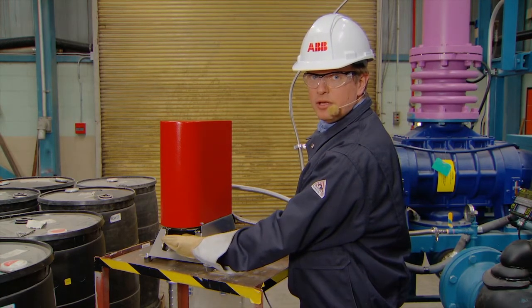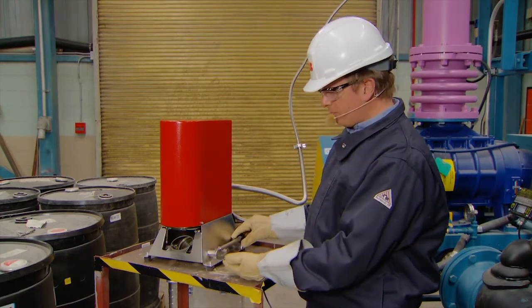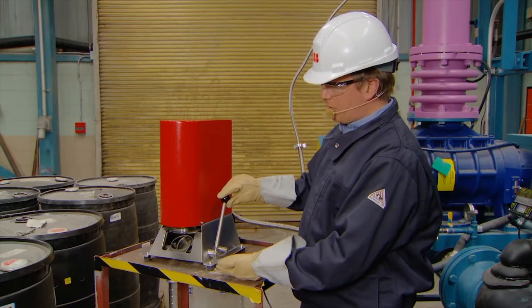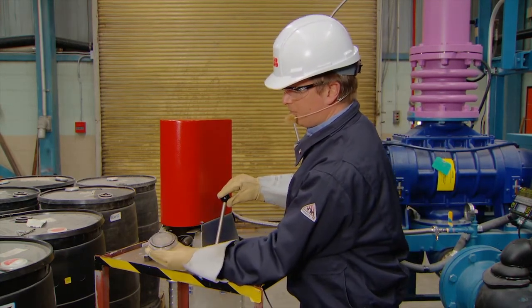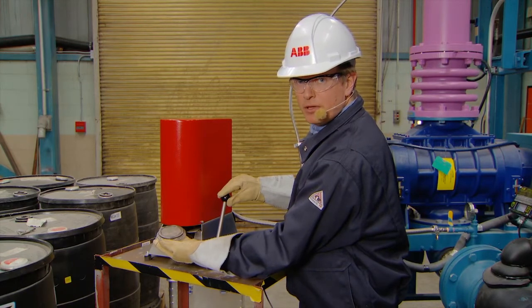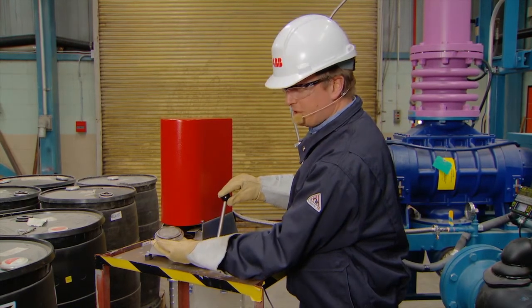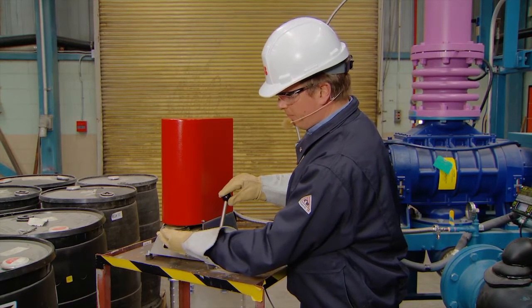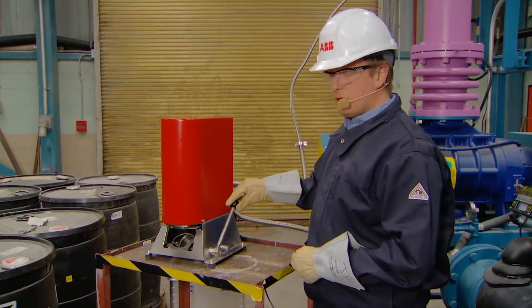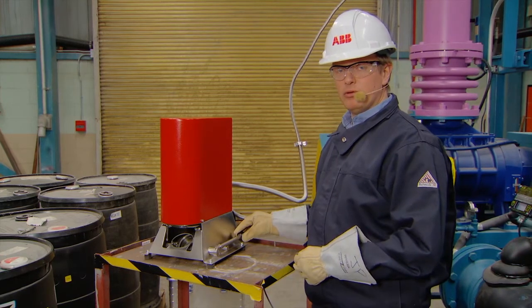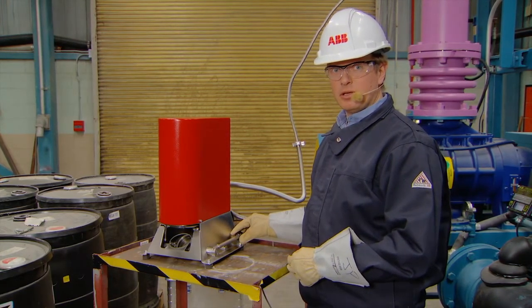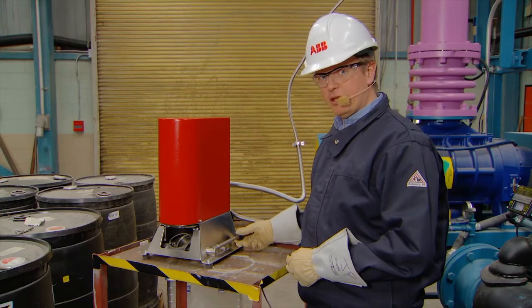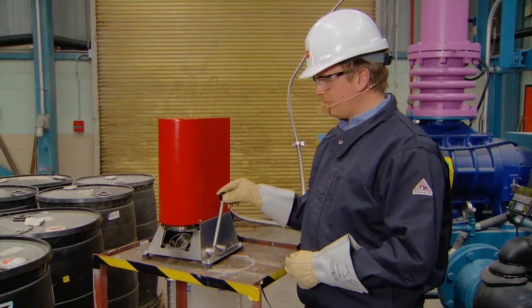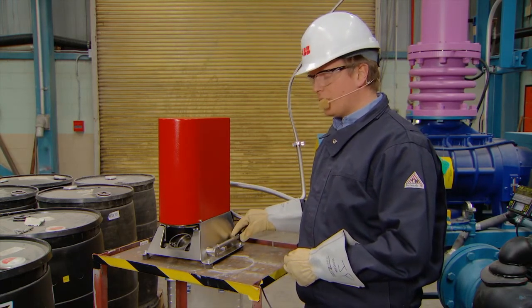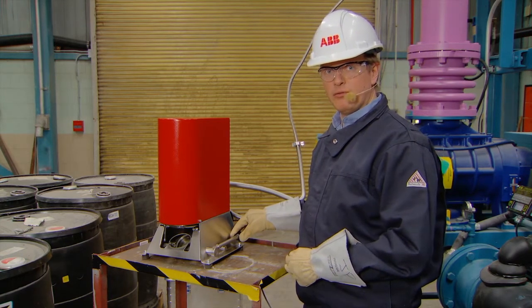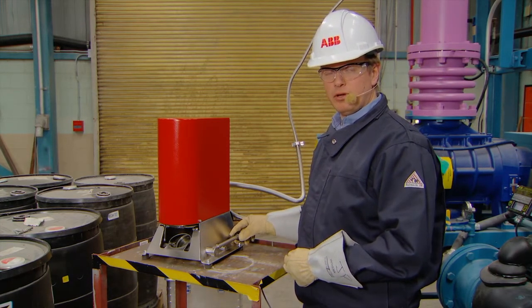You can exchange the powder by opening the lever, take out the glass, and exchange the powder. When the powder is exchanged, put the glass in again and pull down the lever. Notice that very little force has to be used when operating the lever. If extensive force is needed, you'll probably have vacuum in the chamber, and there is a major risk that you break the glass.